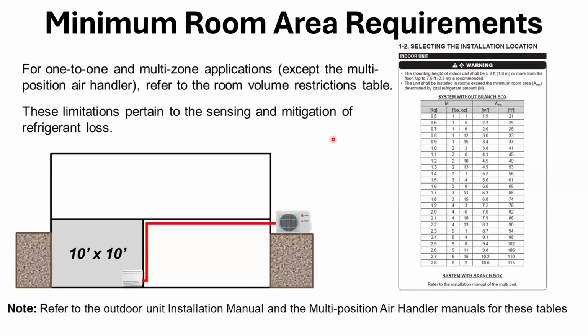And that's where we get into these requirements here. So, minimum room area requirement. There are terms they use: AMIN, which is your minimum area required, and MMAX, which is your maximum charge in that outdoor unit. That unit will be allowed for that minimum area required. So it's pretty easy. After you look at this 5 to 10 times, it makes more sense. If you're just looking at this for the first time, there's some confusion, but it's not that bad. So again, this is for 1-to-1 and multi-zone applications, except the air handler. When you get to the air handler, that's where the difference is.